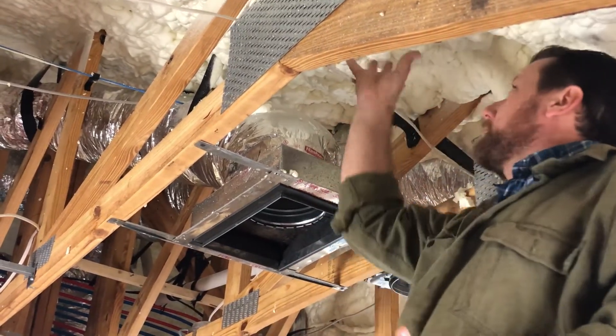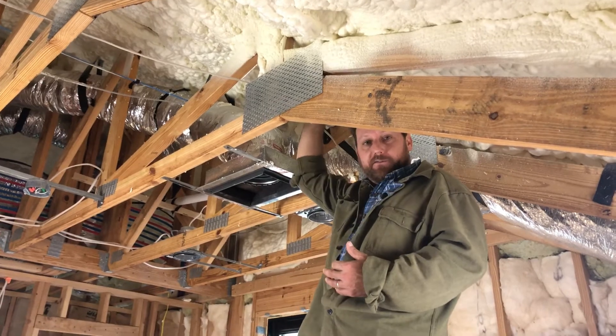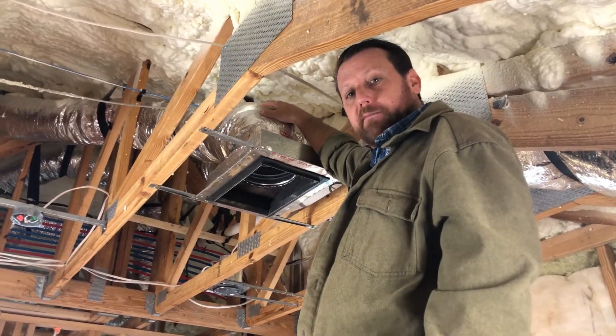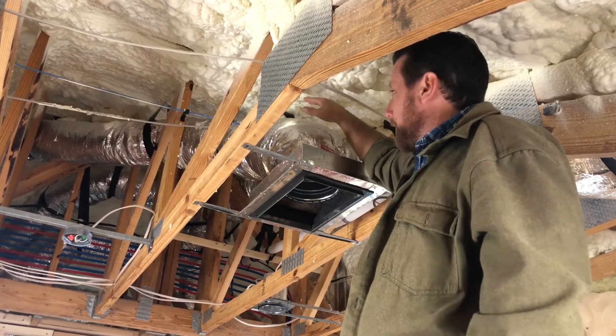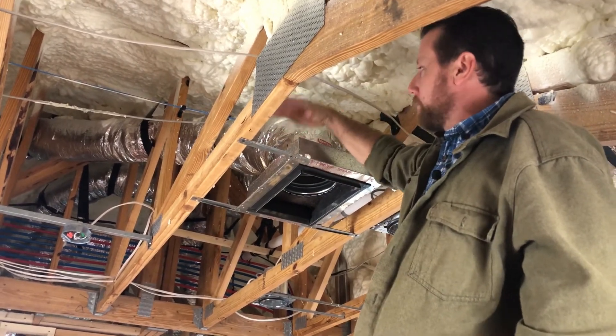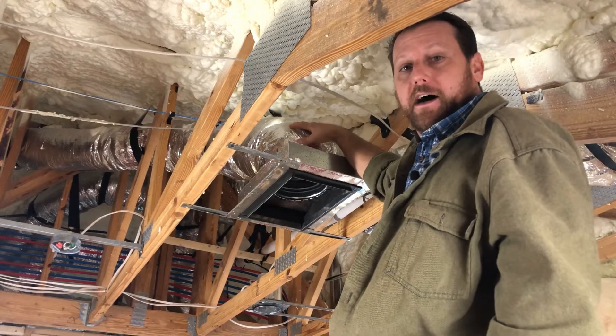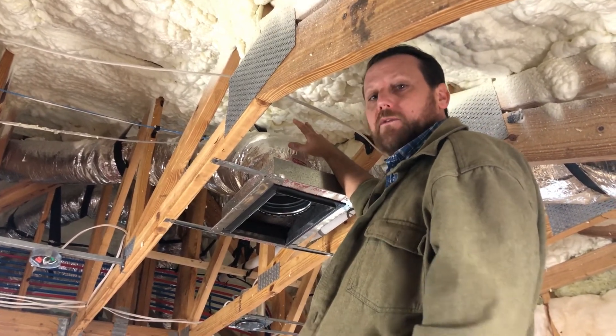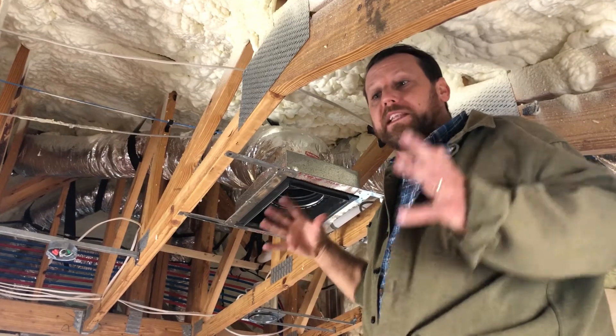In this particular house, we have insulation right up against the roof deck. That adds something incredibly energy efficient for this home because the ducts are technically in the attic, but this attic is not going to be 110 degrees like most attics are. This duct is now in an environment within the insulation envelope — the thermal barrier is up at the roof deck and the duct is below it. In a lot of houses, blown-in fiberglass or batts at the drywall ceiling is the thermal barrier, leaving a very hot attic with ducts running through it. Any pinhole or imperfection in those ducts in a hot attic means significant energy loss, and you also have a much greater chance for vapor and moisture to build up.